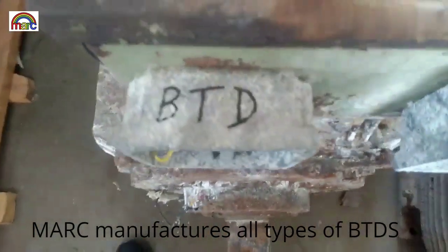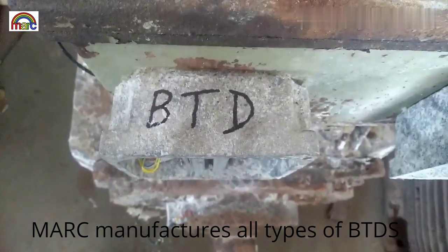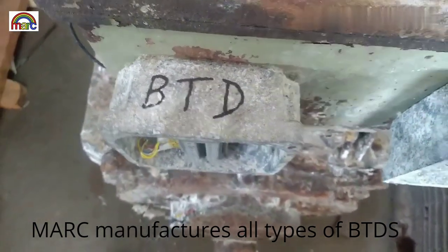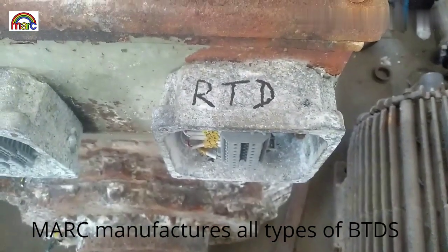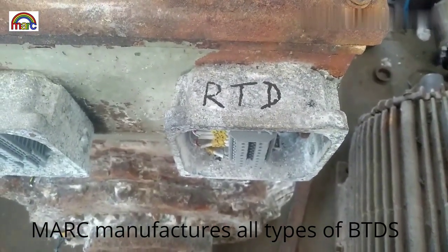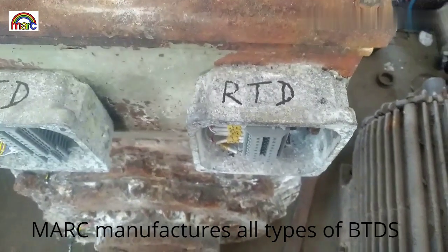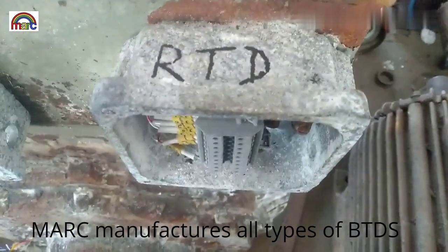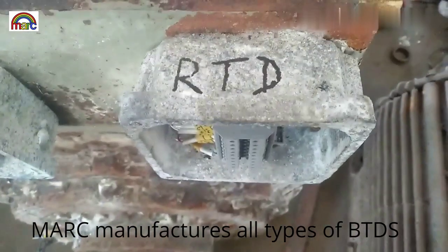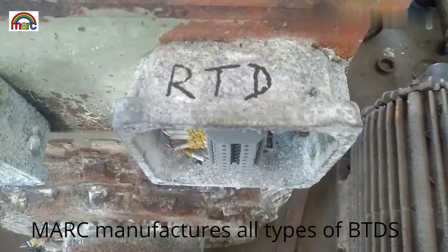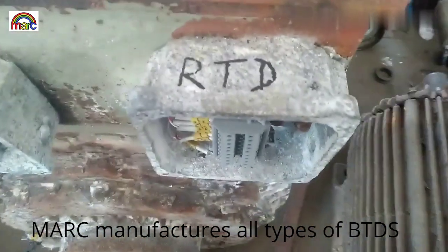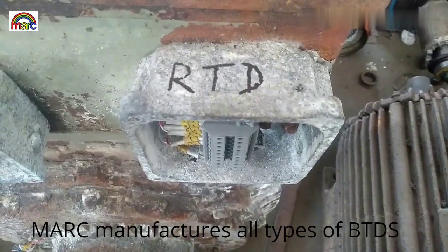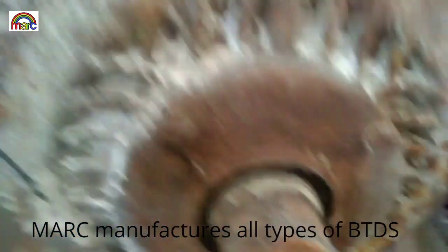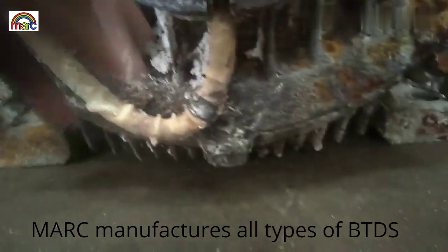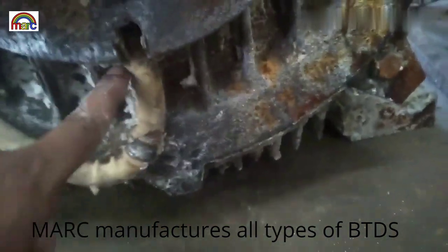BTD is nothing but bearing temperature detector. Normally in rotating machines we have BTDs and RTDs. RTDs, called resistive temperature detectors, are used for winding temperature detection, and for bearings those are called bearing temperature detectors. So in this topic we are going to cover bearing temperature detectors.